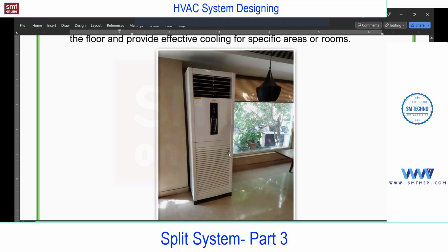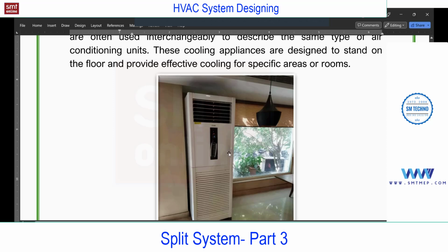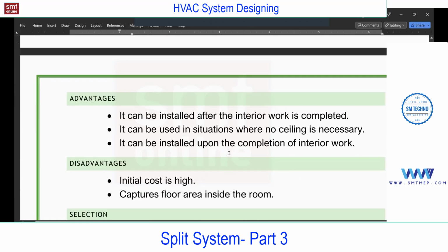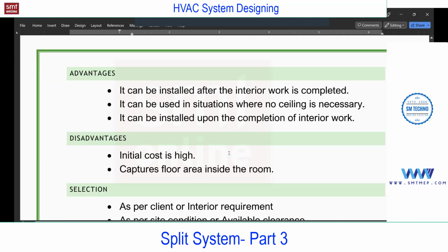You will not find this commonly. Most commonly, you will find high wall or, from an interior point of view, cassette. In some projects, you may find this, or you can suggest it as an engineer as per the situation. Let me complete the advantages first. Advantages: it can be installed after completing the interior work. It can be used where no ceiling is required, without a false ceiling, because it does not require any ceiling. Suppose there is no false ceiling, so one can use this one. It can be installed after completing the interior work, as I've just given.